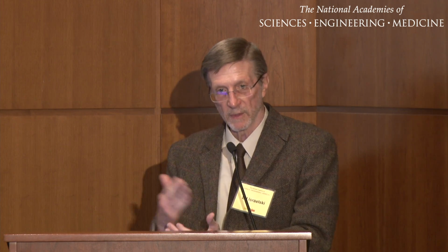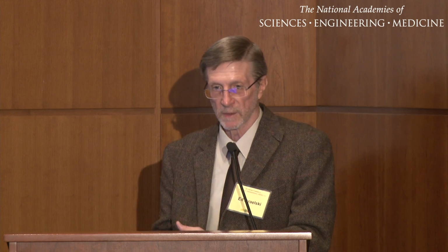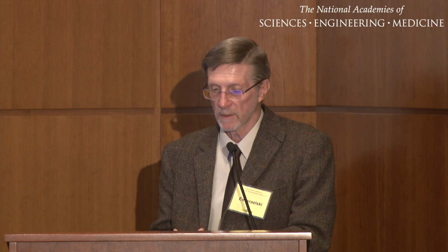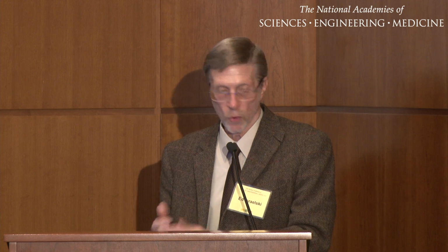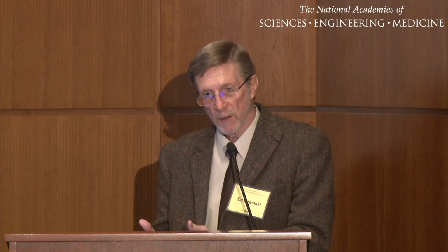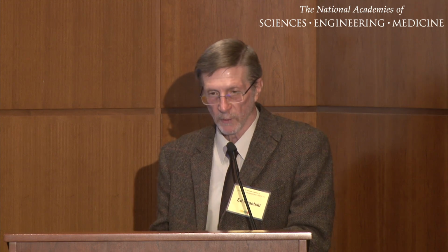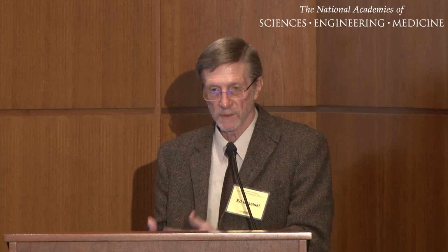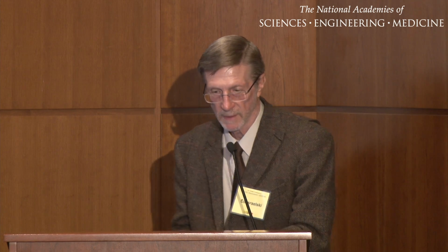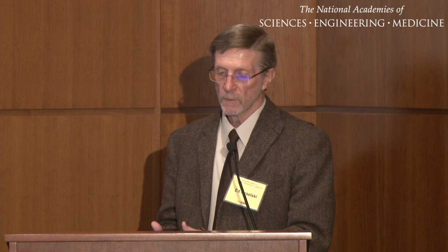So the first one, application of usability engineering to medical devices, is a process standard. It elaborates on that flow chart that I showed and the points that Irene covered earlier, and it's normative. It has shall statements in it saying you must do these following things, like you must do risk management, you must do usability evaluation of some kind. Part 2 came out this year, 62366-2.